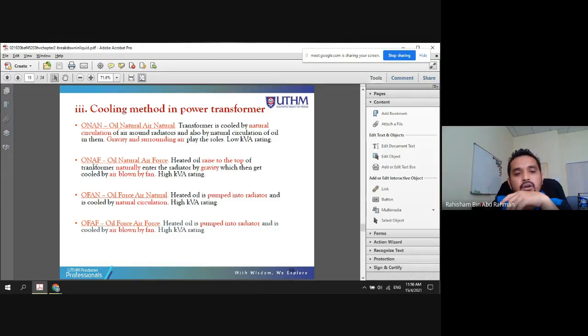Then we have ONAF, oil natural, air force. Oil natural means the transformer oil within the tank is allowed to move naturally, but in this case we use an external fan to cool down the transformer from outside. We use a fan to blow wind onto the wall of the transformer, and then the liquid dielectric or transformer oil close to the tank, with the air blown through it, becomes cool and circulates within the transformer.